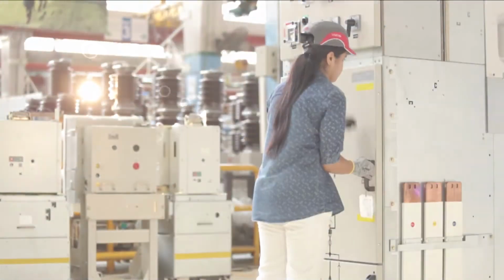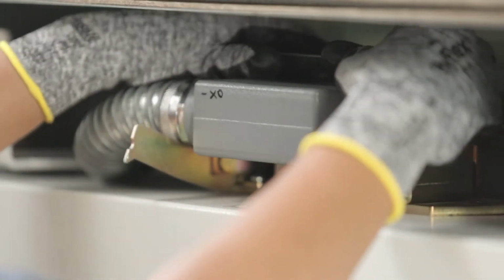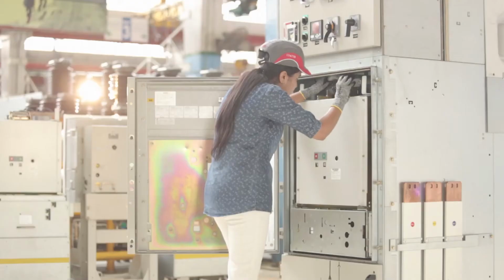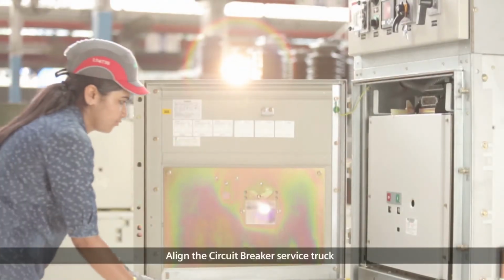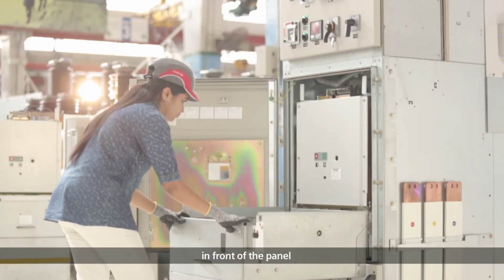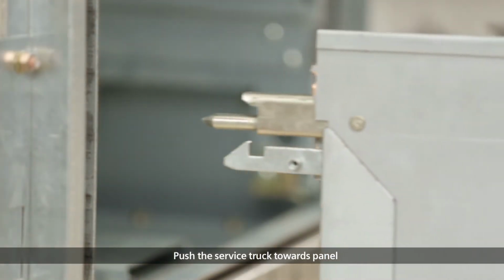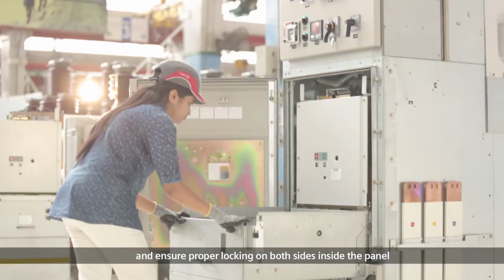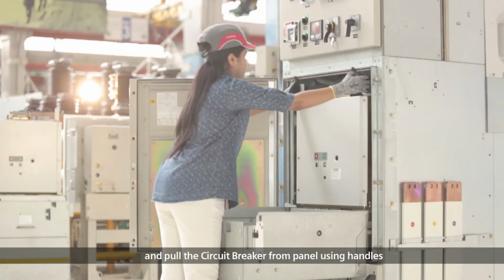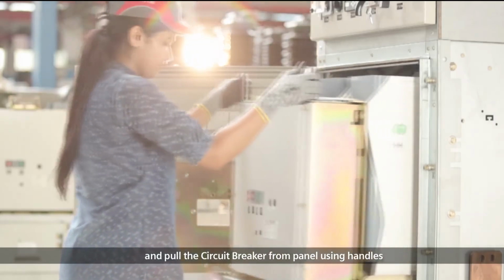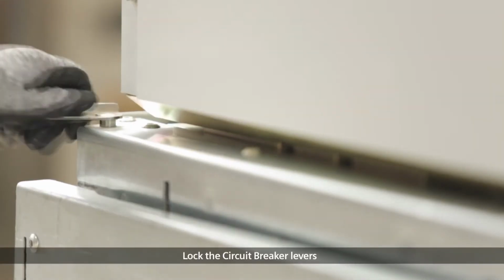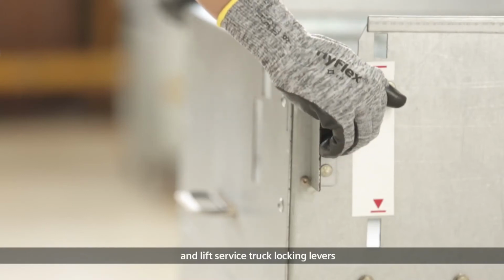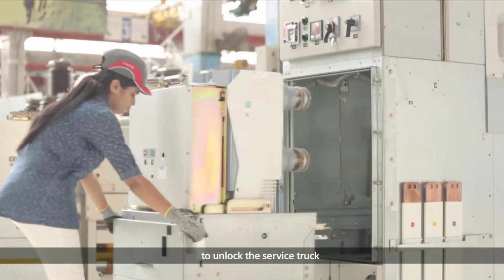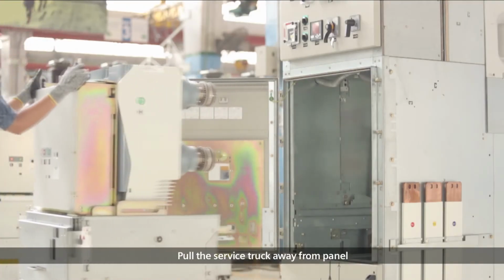Procedure for removing the circuit breaker from the panel. Align the circuit breaker service truck in front of the panel. Push the service truck towards panel and ensure proper locking on both sides inside the panel. Unlock the levers and pull the circuit breaker from panel using handles. Lock the circuit breaker levers and lift service truck locking levers to unlock the service truck. Pull the service truck away from the panel.